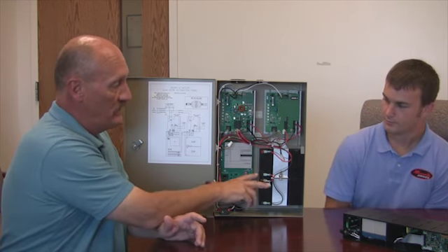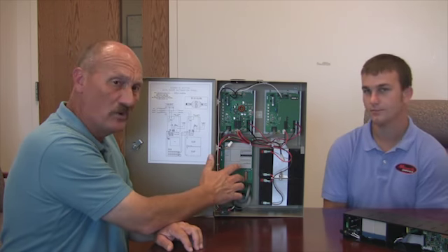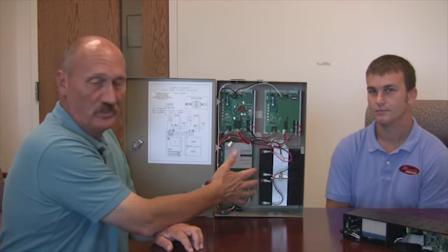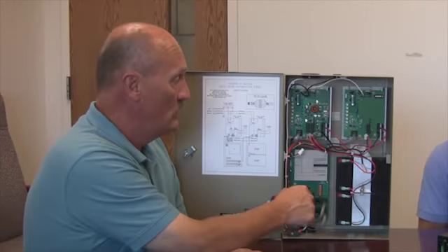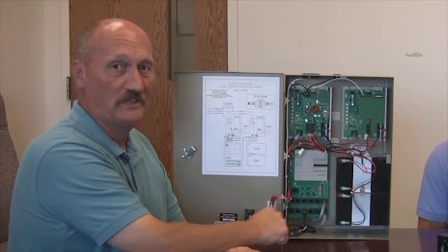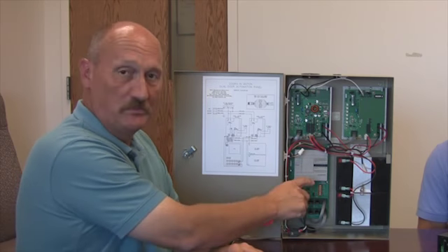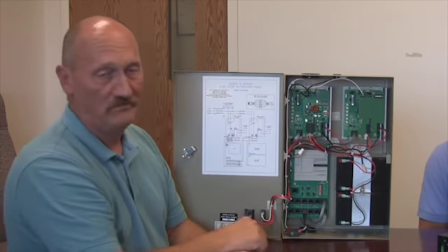That facilitates a DC backup in the event of a power failure, which will keep the PLC powered and will allow the automation control to continue to operate for up to 24 hours when there's no AC available. So before, two PLCs, no battery. After, half of a PLC, custom I/O, also designed and produced here, and added functionality of a DC backup. So this is one really good example of a custom adaptation of a catalog product, in this case HTL.